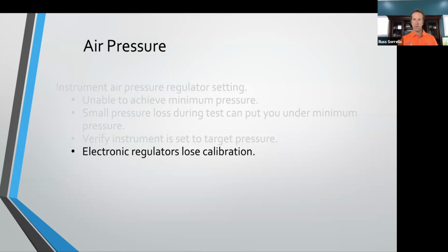But nowadays, what Gordon is explaining to us is that even though the test operated at 48 psi, the instrument is smart enough to adjust what that flow rate out of that leak standard would have been at 50 psi. So it is much more likely to match if everything is calibrated properly.